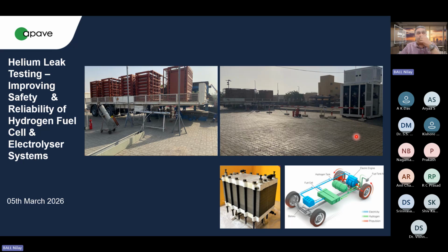And you won't believe it, 3 years back, we found almost 37 leakages in this one unit. And those 37 leakages, when we arrested them, when we changed the design of the joint and tightened the joints, till date there has not been a single leakage. And that's why I say, with a lot of emphasis, that helium leak testing using 100% helium is the best thing that could happen in any hydrogen system.